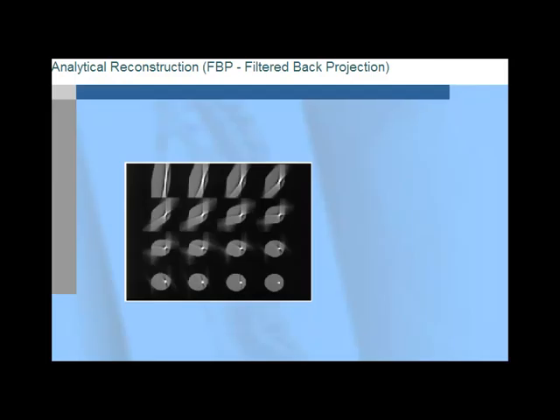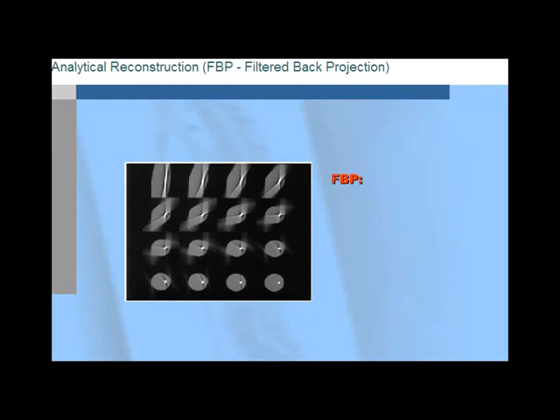When we break down various technological components of PET and discuss reconstruction, we can't skip filtered back projection, or FBP. By processing each individual projection with a filter prior to back projection, FBP improves overall quality. This method is fast and uses less computing power. Furthermore, despite the fact that more elegant, iterative, and analytical techniques have been devised, FBP is still widely used in commercial instrumentation because of history and its ease of use and implementation.